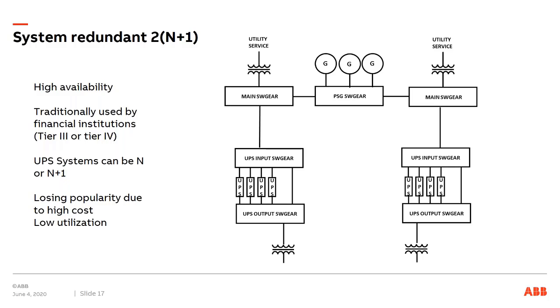So it works great, and it's very highly available, very high availability. The drawback is that the utilization is low. Utilization has become a buzzword in the industry over the last several years, because for this to work, you have to be able to lose the entire left side, and the other side has to be able to support the load, ideally still with redundancy on the UPS side. As a rule of thumb, the utilization of everything is less than 40%.